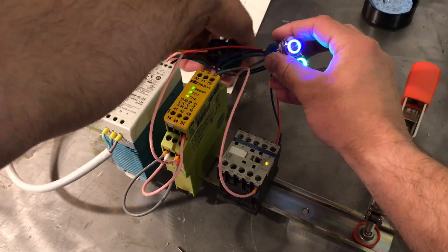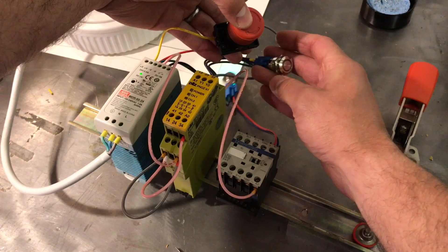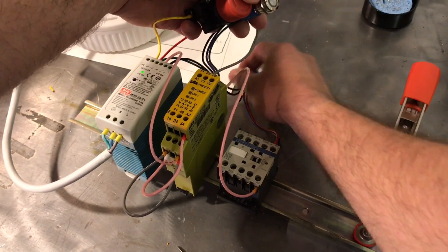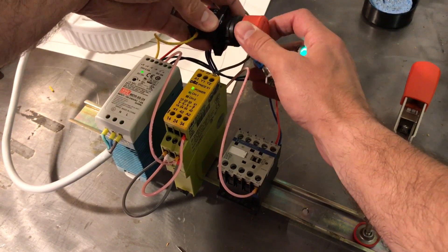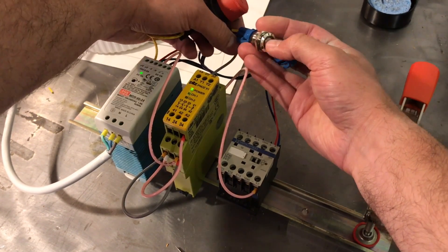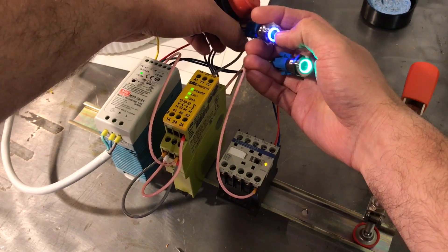When everything's on, if the e-stop is pressed, power's cut to everything. The light remains on here to say that if you reset this and press the reset button, the contactor will immediately come on. So that light being on is useful.